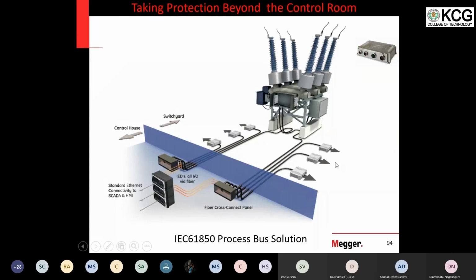This arrow mark is the copper cable. This is going to convert the copper analog value to digital value, and this fiber cable is an armored fiber optic cable which is connected to the cross connect panel, or you can say the Ethernet switch. From the Ethernet switch, this fiber is connected here. Now there is another point here. This is black in color, but this is also fiber optic cable. This is not copper cable. This is armored, military standard armored fiber optic cable, so that the rats cannot bite. So what are the advantages?